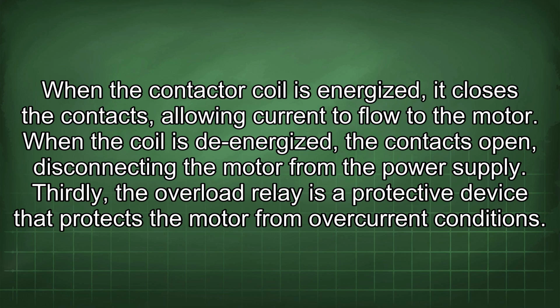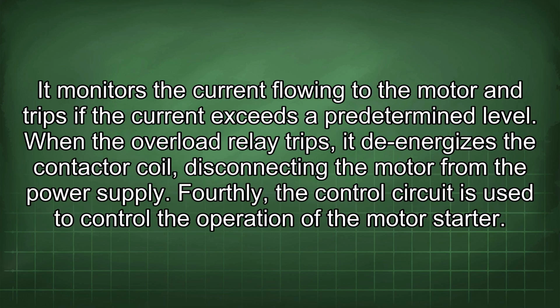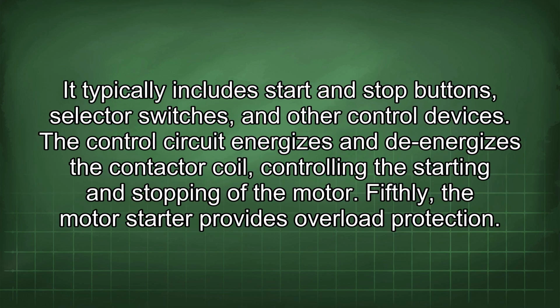Thirdly, the overload relay is a protective device that protects the motor from overcurrent conditions. It monitors the current flowing to the motor and trips if the current exceeds a predetermined level. When the overload relay trips, it de-energizes the contactor coil, disconnecting the motor from the power supply. Fourthly, the control circuit is used to control the operation of the motor starter. It typically includes start and stop buttons, selector switches, and other control devices. The control circuit energizes and de-energizes the contactor coil, controlling the starting and stopping of the motor.